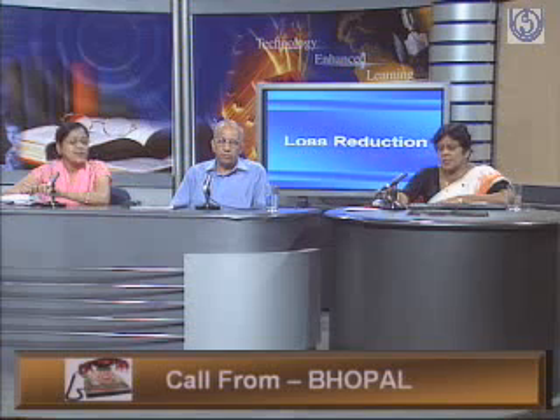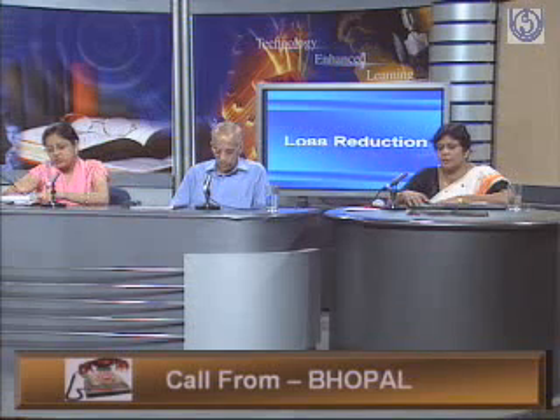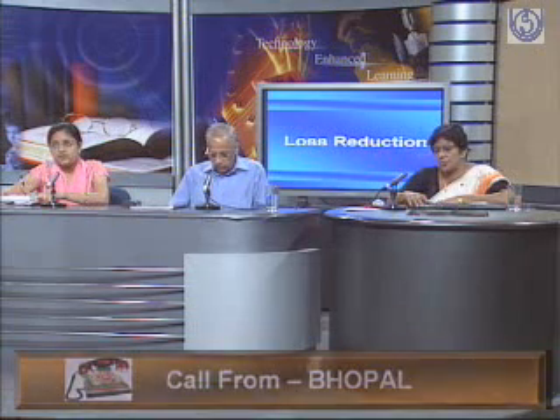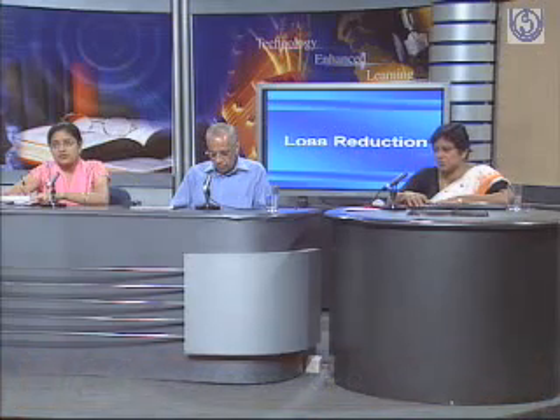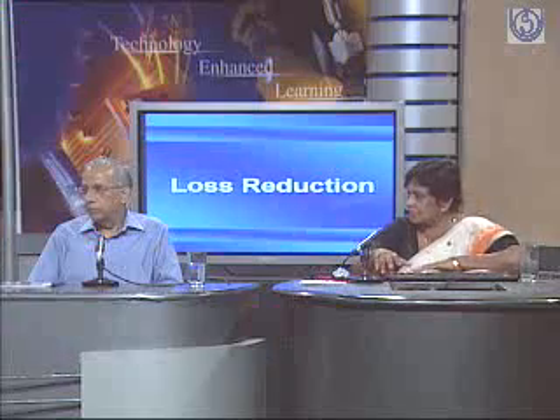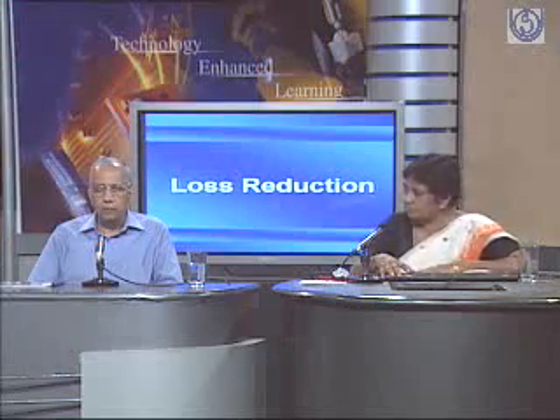These DC transmission lines are not being used in the sub-transmission and distribution system. They are only used in the transmission system. The losses are lower, and you use DC for transmission of huge blocks of power from one region to another. The criterion is more towards transfer of huge blocks of power rather than loss reduction. Mainly, though, losses in DC will be less compared to the AC system. In a high voltage line, corona loss will be less.